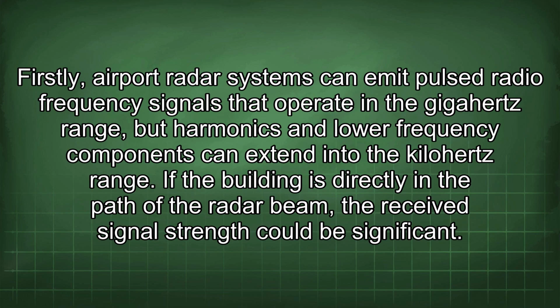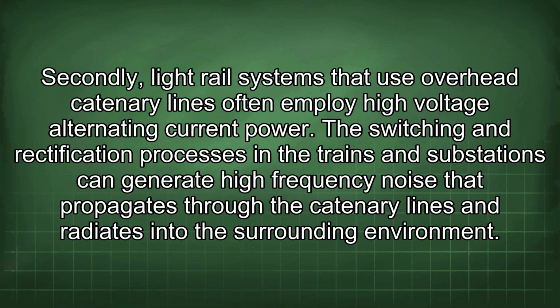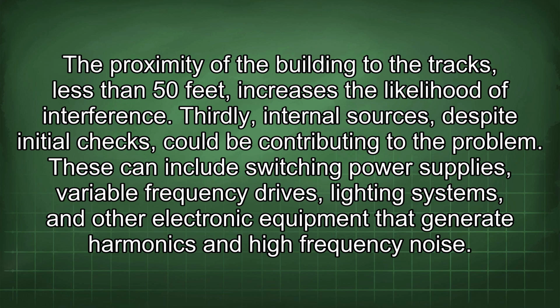Firstly, airport radar systems can emit pulse radio frequency signals that operate in the gigahertz range, but harmonics and lower frequency components can extend into the kilohertz range. If the building is directly in the path of the radar beam, the received signal strength could be significant. Secondly, light rail systems that use overhead catenary lines often employ high voltage alternating current power. The switching and rectification processes in the trains and substations can generate high-frequency noise that propagates through the catenary lines and radiates into the surrounding environment. The proximity of the building to the tracks, less than 50 feet, increases the likelihood of interference.